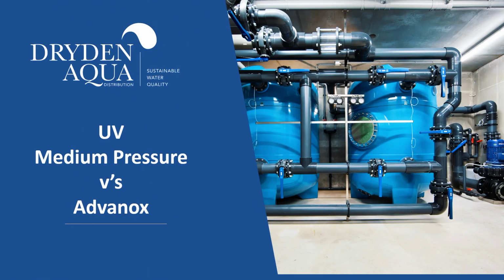I would like to compare now medium pressure UV versus our Advanox system, because medium pressure UV is often recommended in the UK, first of all, to create a barrier against Cryptosporidia, because it will inactivate Cryptosporidia, but also to take out combined chlorines. But there is a side effect to that. With AFM DAISY, we create a barrier against Cryptosporidia, so it negates really the need for medium pressure UV. But we still get a build-up of organic chloramines in the water that need to be dealt with.